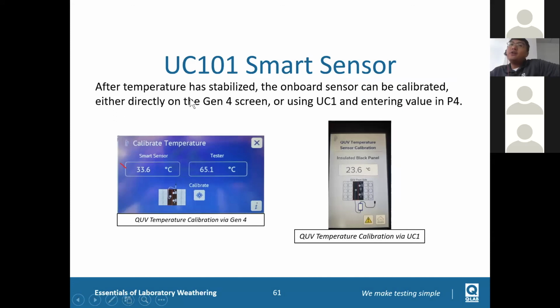After the temperature has stabilized, the onboard sensor can be calibrated either directly on the Gen 4 screen or using UC1 and entering the value in the P4 expert parameter. Okay, that's done. That's much easier, and the result is more reliable, because it is the same structure compared with your onboard sensor. So this calibration makes better sense compared with the old one. Do remember that the temperature of the QUV still needs to be recalibrated.